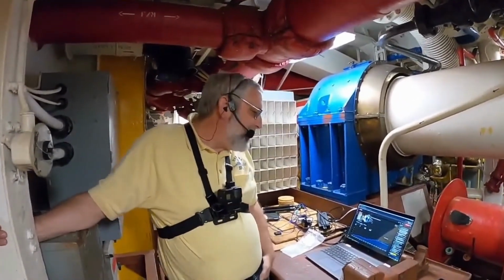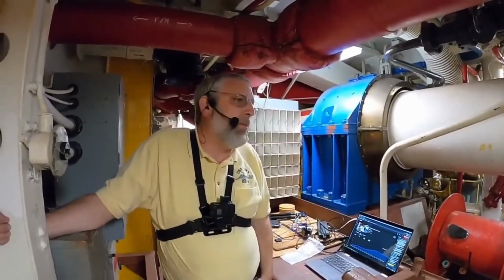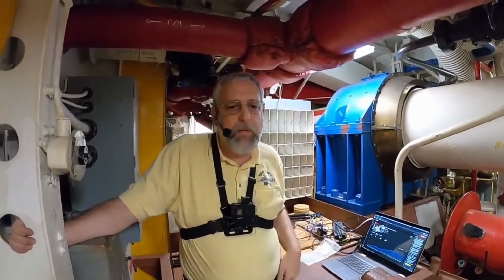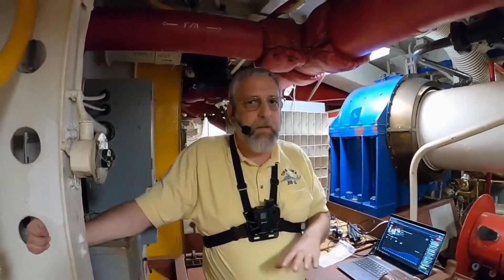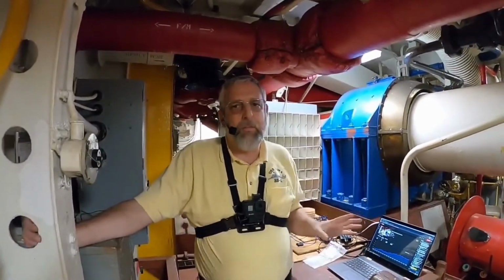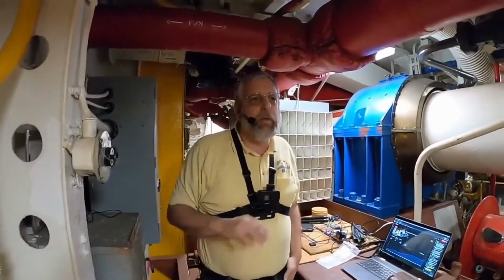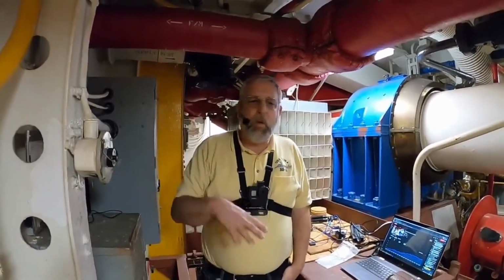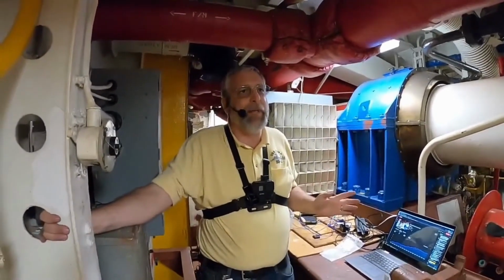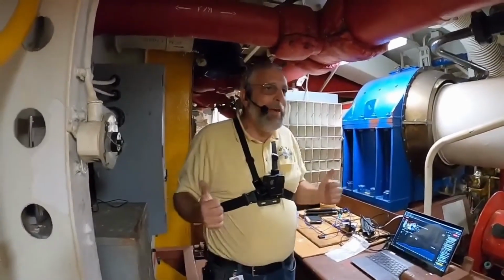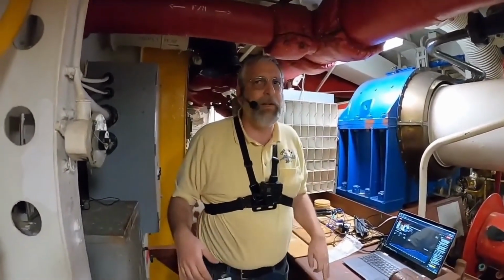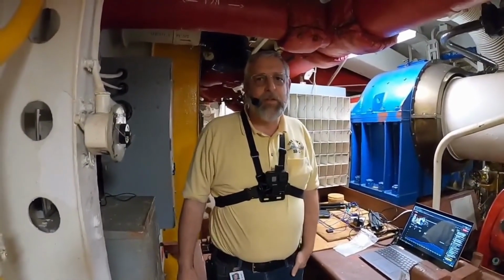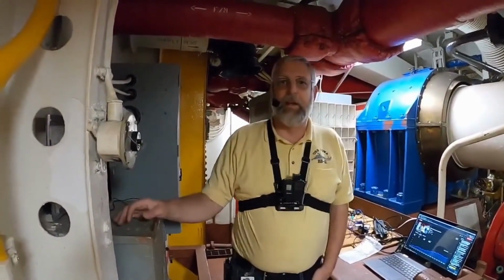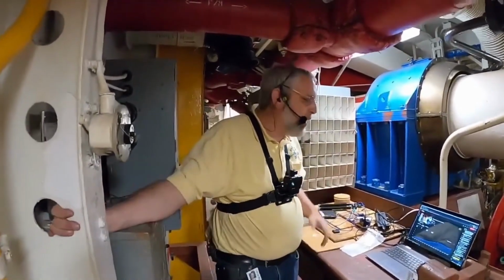Next question: did I treat feed water? That was the other thing I did, I ran the distilling plant. Yes, we absolutely treated the feed water to the boilers, and there was a whole water lab to do that. To this day, 0.02 parts per million of any contaminant was the limit for water going to the boiler. We could have worse water going to the humans, but the boilers got less than 0.02 parts per million of any contaminant, including salt, made out of the distilling plant. I was on a recent modern Navy ship and asked where their distilling plant was. They said, what are you talking about, we don't have a still, we use reverse osmosis. I hate you, because we boiled our water and then condensed it.